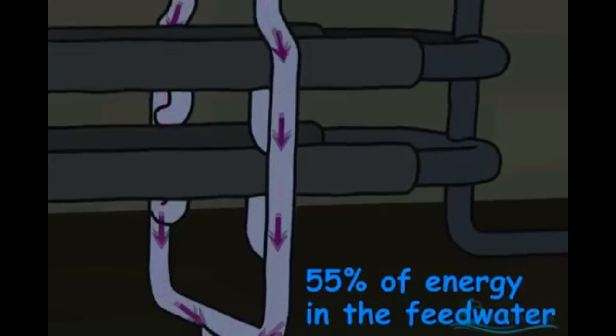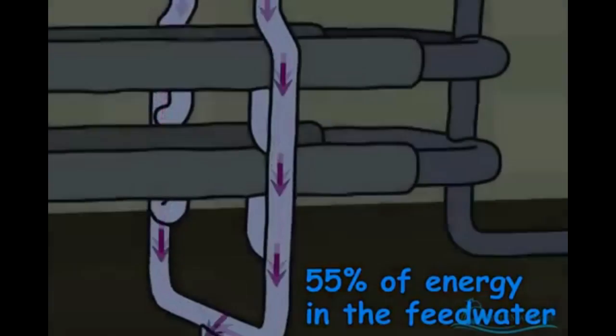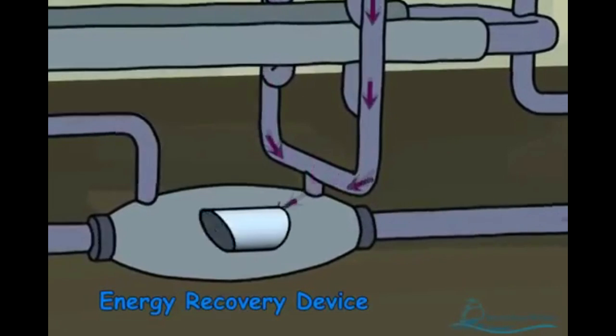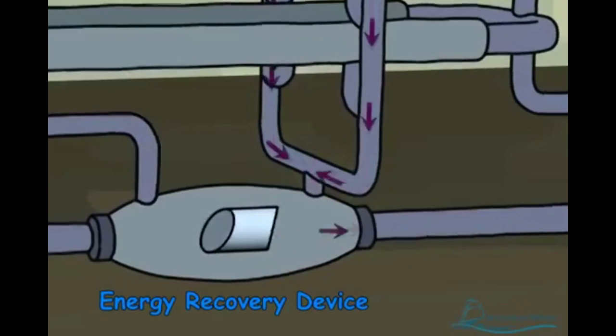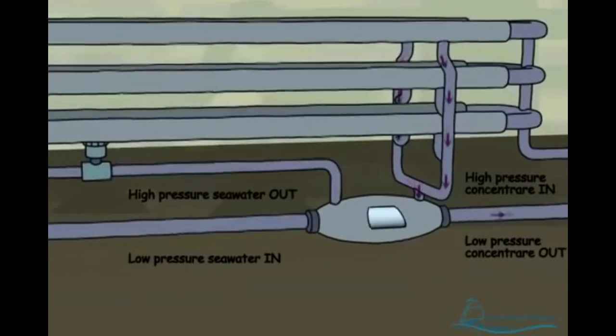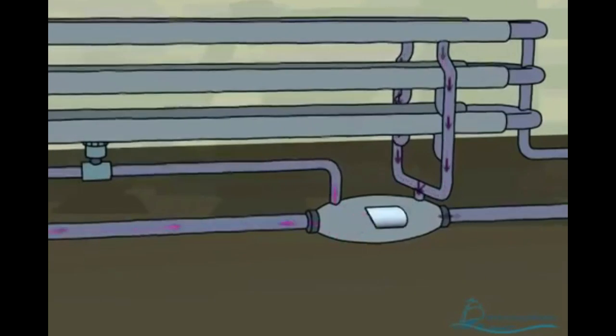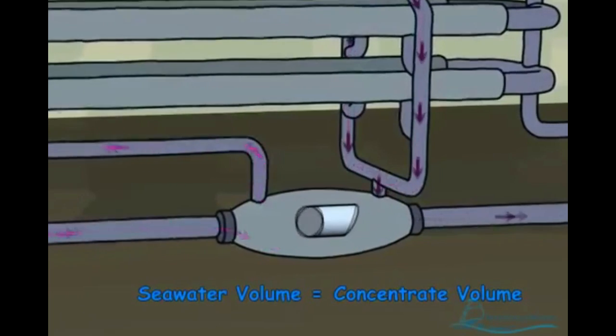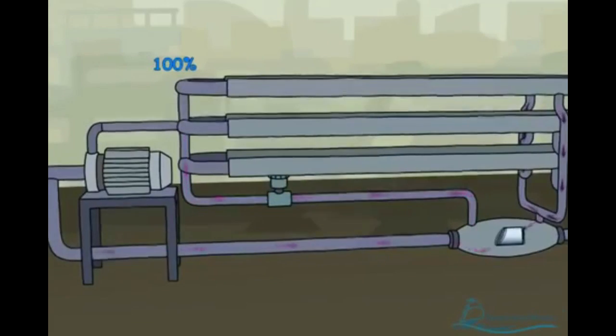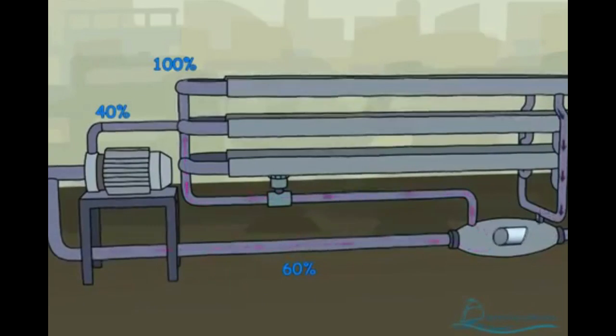The concentrated salt stream retains about 55% of the total energy of the seawater stream that was originally fed to the membranes. To reduce the energy required to operate the reverse osmosis plant, the pressurized concentrated stream is piped into an energy recovery device. Here, up to 98% of the energy of the concentrated salt stream is transferred to an equal volume of incoming seawater in an isobaric energy recovery device. This significantly reduces the plant's operating costs by recovering that energy and using it to pressurize 60% of the seawater that is fed to the membranes.